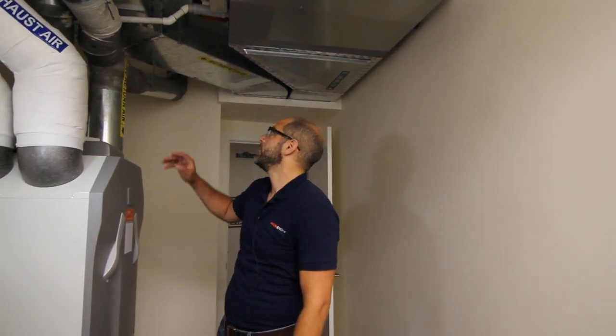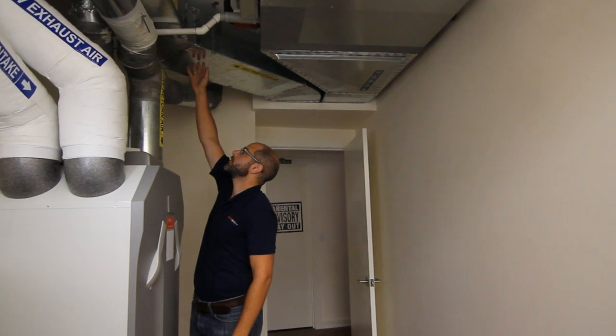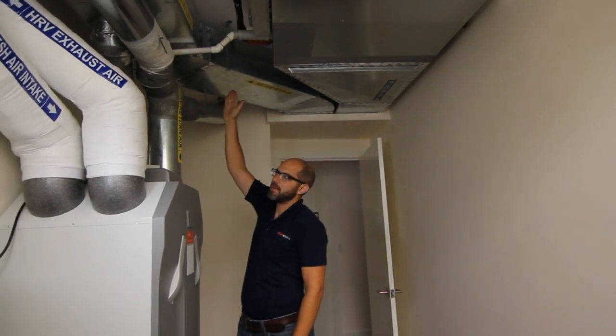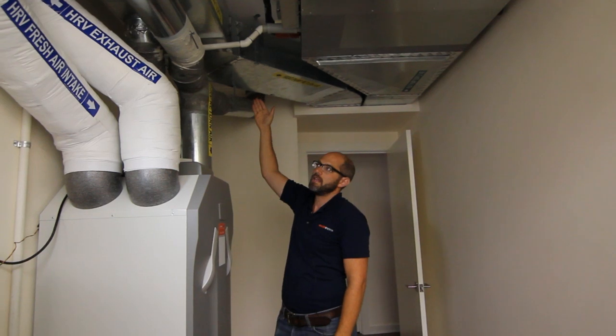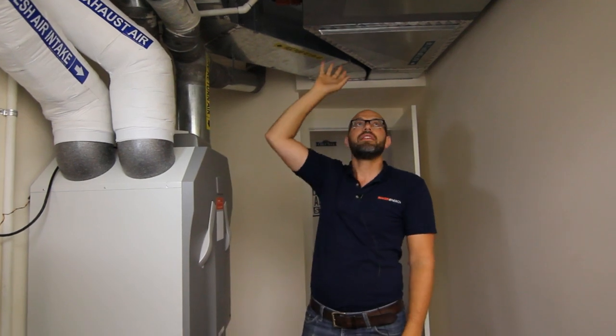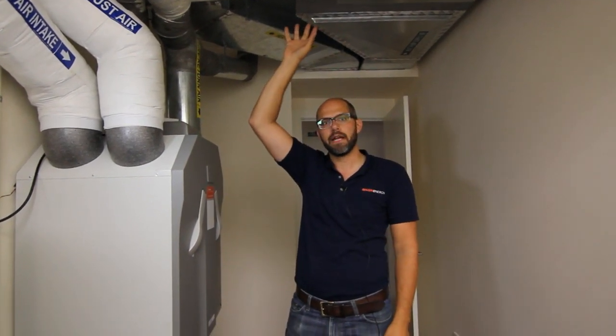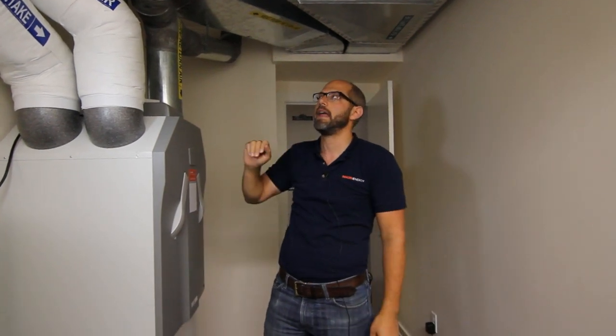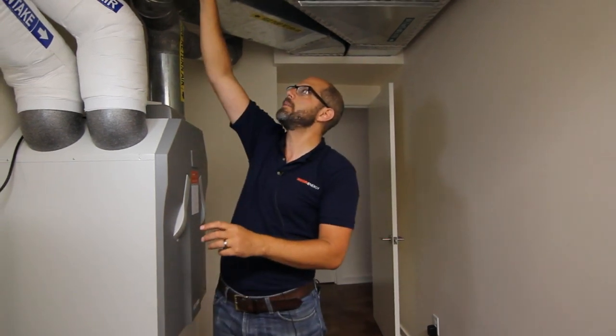One of the other functions we have here, which you can't really see, but it's in this little space here, is a damper that's actuated on pressure. The reason that we have that there is so that when the air handler is off, not providing heating and cooling, when there's not a need for heating and cooling in the house, we still want to ventilate. But we want that ventilation air to get to all the different rooms in the house.